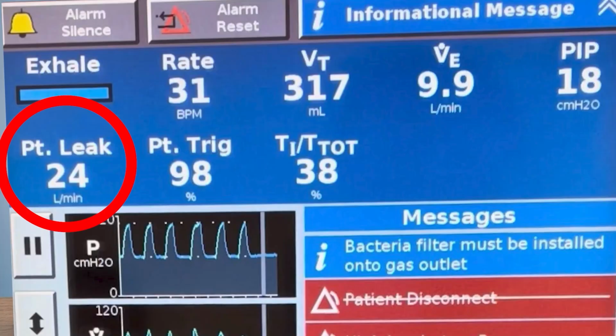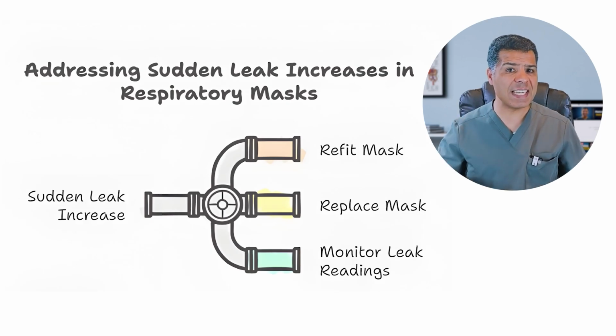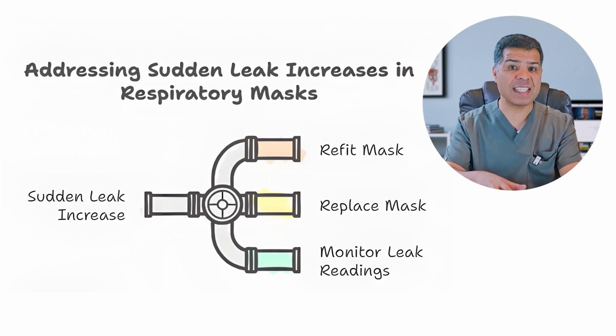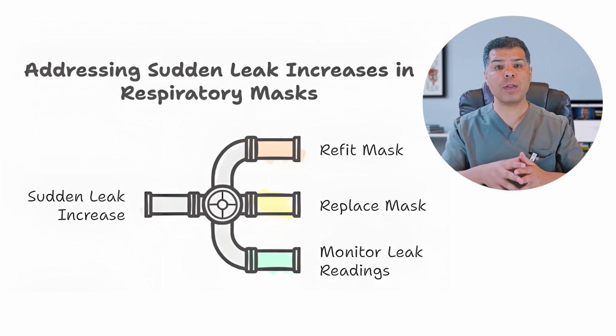And what you see displayed on the machine screen here is the total leak, which is the sum of both intentional and unintentional leak. There is no universal standard for what leak rate is acceptable, since it depends on the specific device and the specific mask interface. However, if the leak becomes excessive, it can lead to under delivery of tidal volume and ineffective ventilation. Pay attention, a sudden increase in leak without any change in pressure settings should raise concerns. In such cases, ask the respiratory therapist to refit or replace the mask and closely monitor the leak amount.